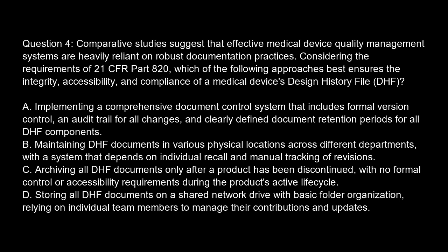Considering the requirements of 21 CFR Part 820, which of the following approaches best ensures the integrity, accessibility, and compliance of a medical device's design history file, DHF? Option A. Implementing a comprehensive document control system that includes formal version control, an audit trail for all changes, and clearly defined document retention periods for all DHF components.